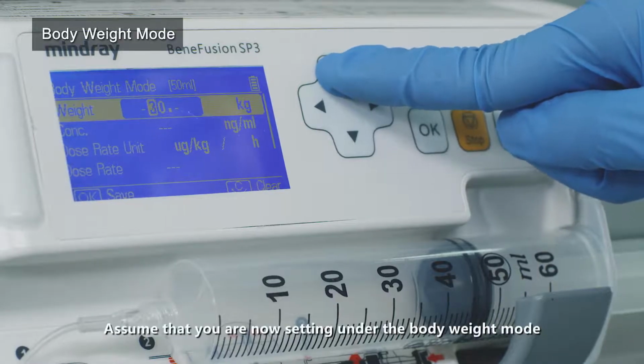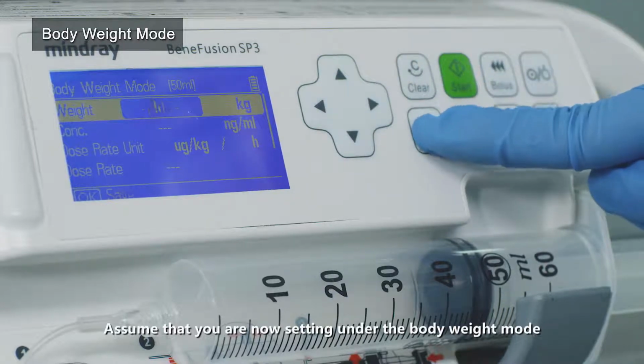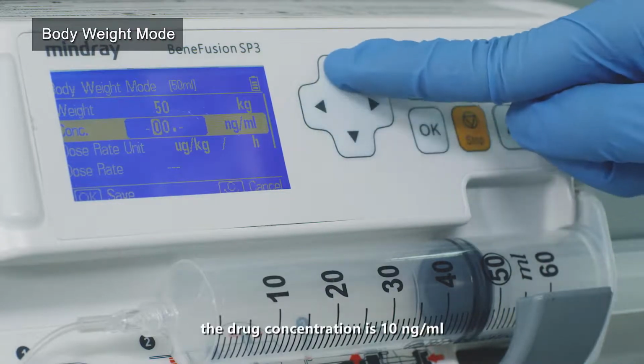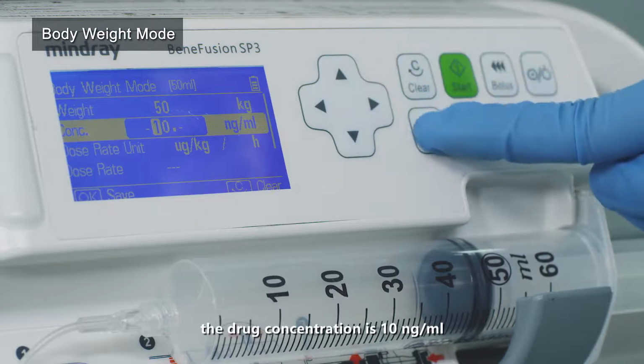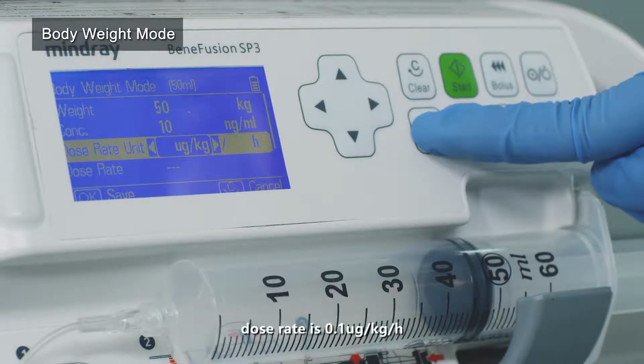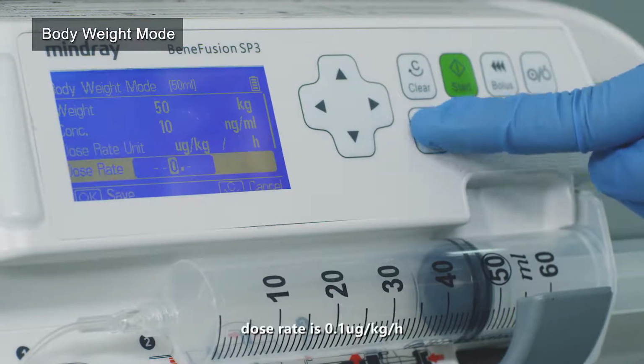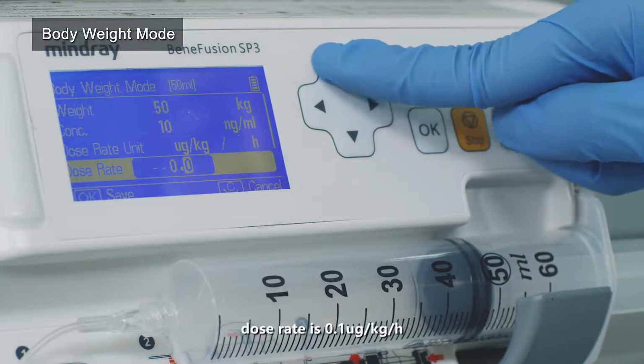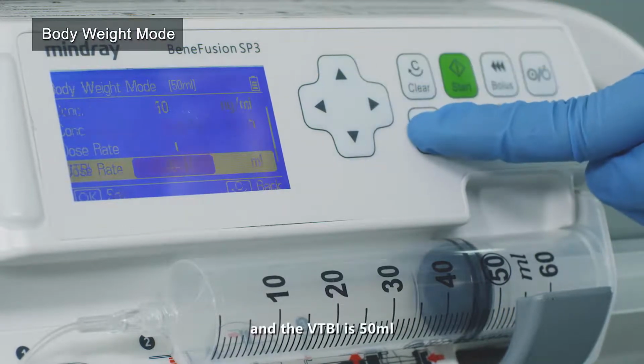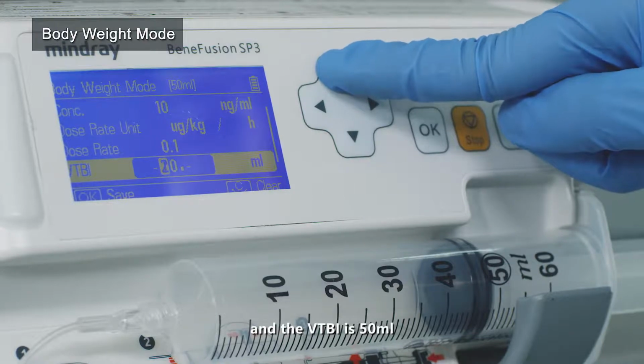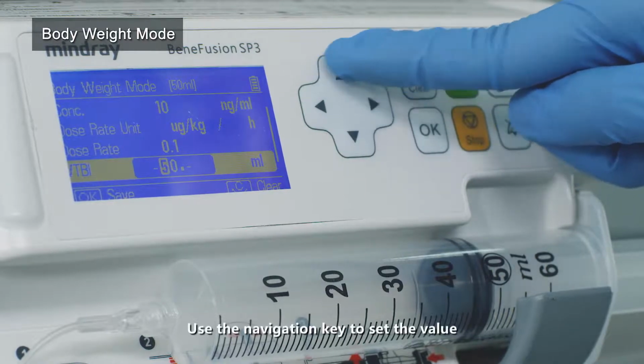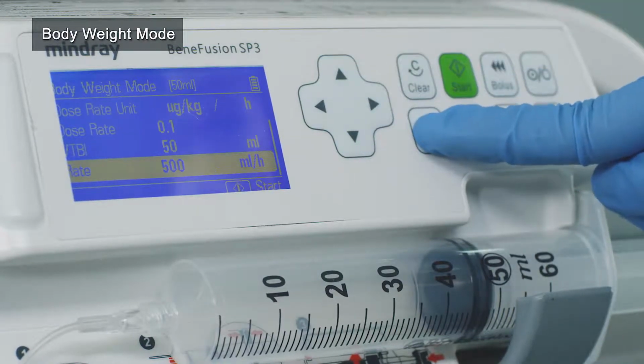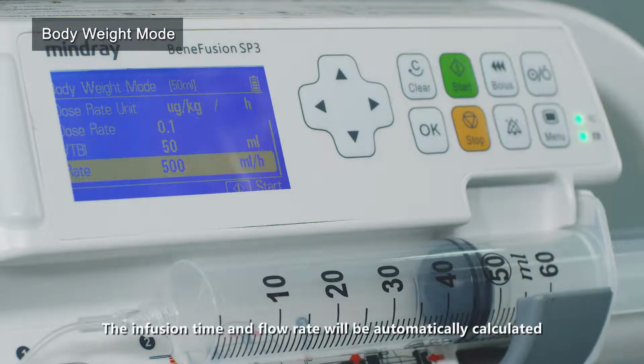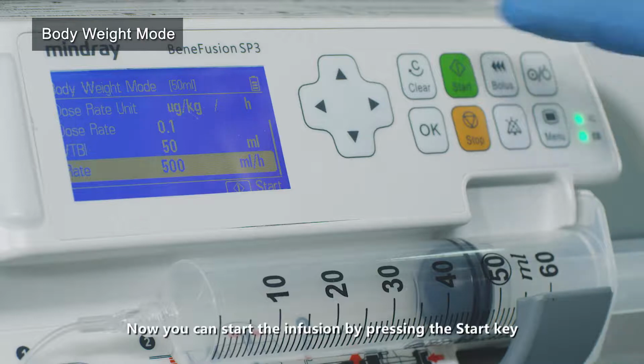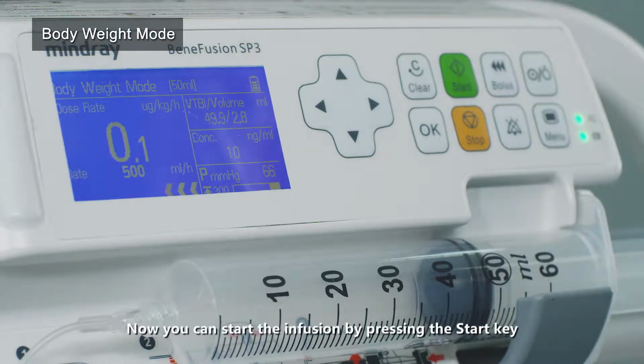Assume that you are now setting under the body weight mode. The drug concentration is 10 nanogram per milliliter. The dose rate is 0.1 microgram per kilogram per hour, and the VTBI is 50 milliliter. Use the navigation keys to set the values. The infusion time and flow rate will be automatically calculated. Now you can start the infusion by pressing the Start key.